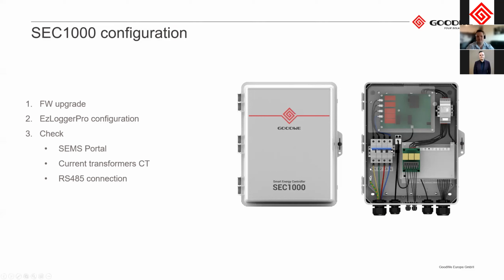So the input here on the device, so live 1, live 2, live 3, the further you are from where your CTs are with your voltage reference, you could have a slight voltage change between your CT readings, and that can also affect the accuracy of the readings you receive. The only reason I mention this is because we have had this in the past, where installers might install this closer to the inverter and run a 20-meter cable for the CTs, and that it doesn't work very well. I can tell you that much.